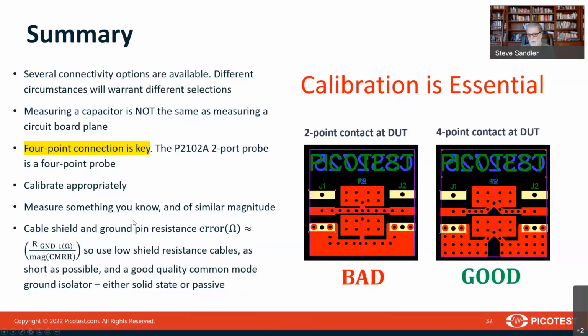The cable shield and the ground pin resistance is really significant, and I didn't talk about that before, but I showed the ground resistance error and how that gets into the low frequency measurement. So we have these shields, and the shield resistance becomes part of the error that we need to calibrate out.